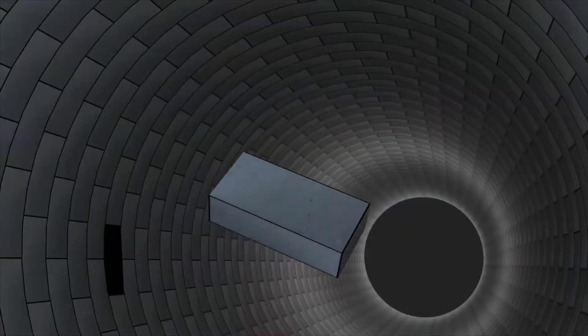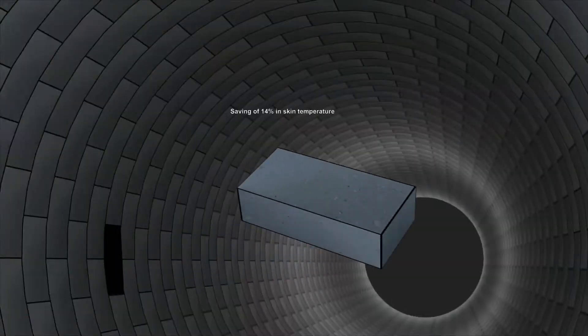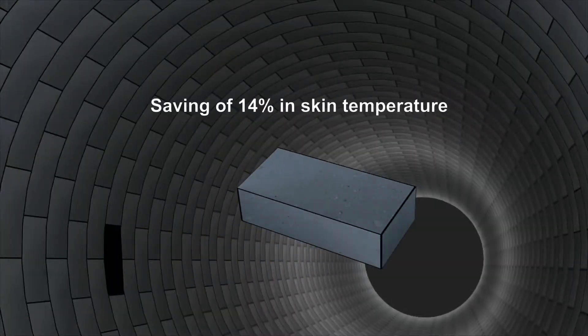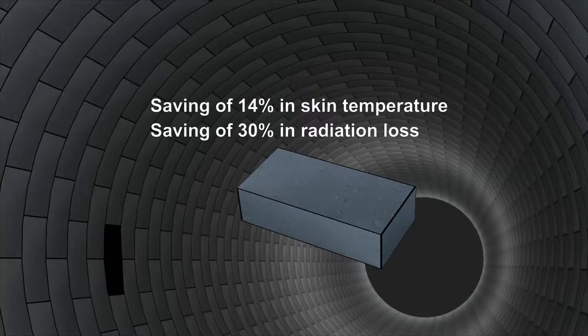Thus, using mullite based castables in place of low cement castables can lead to a saving of 14 percent in the skin temperature and around 30 percent savings in radiation heat loss from the surface.